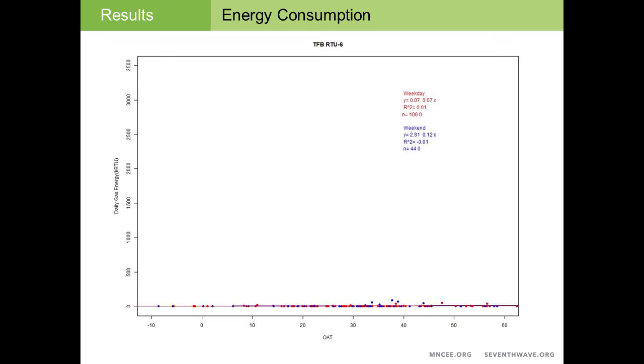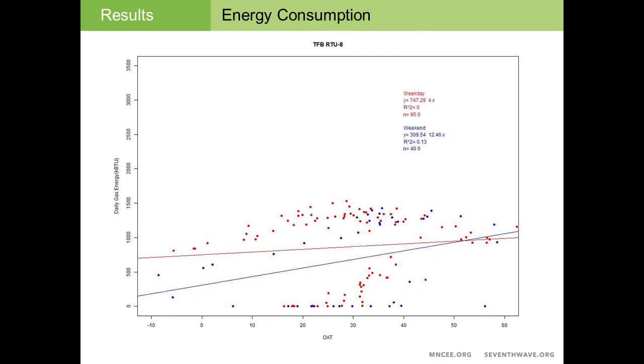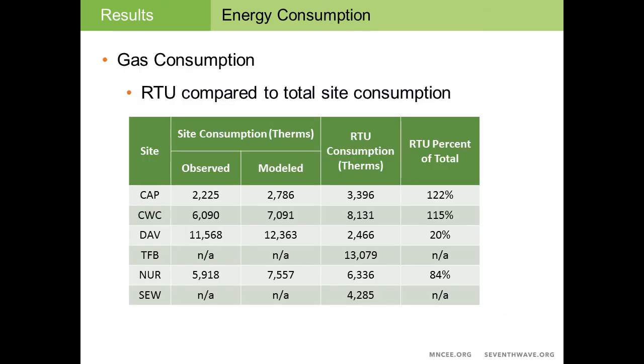Here's a rooftop unit that didn't use any gas whatsoever. It was an interior space. We did test it a number of times to make sure the gas was activated and could be activated from the thermostat, but surrounding rooftop units could have been carrying this load for this particular rooftop. And here's a model that follows no predictable path. There are too many varying loads happening within the space to even develop any type of correlation between outdoor air temperature and energy use.